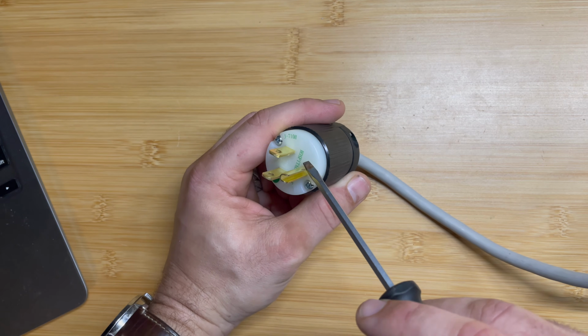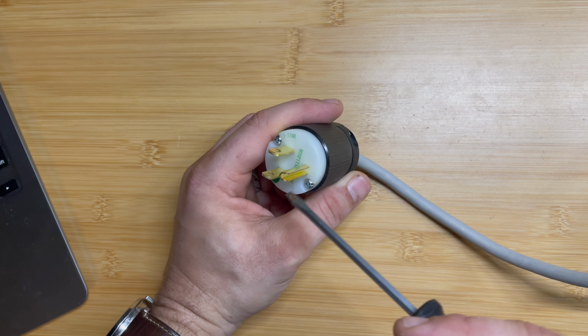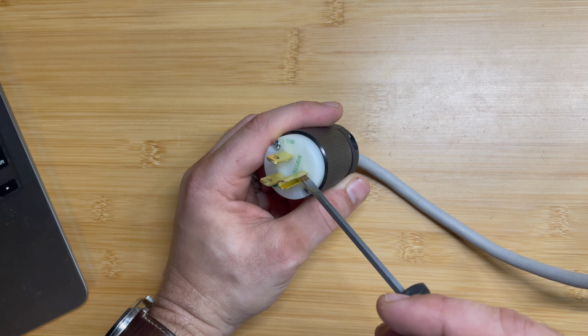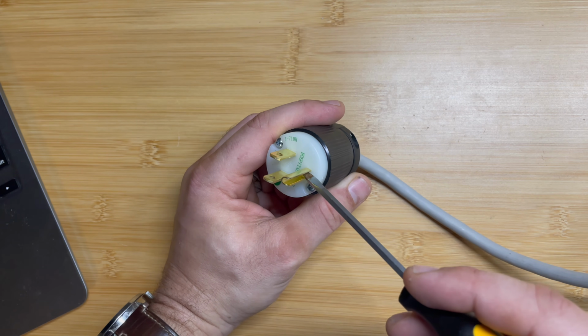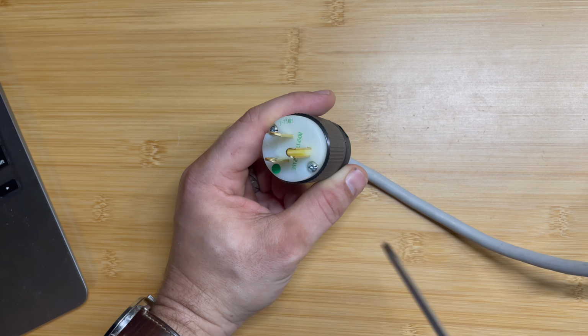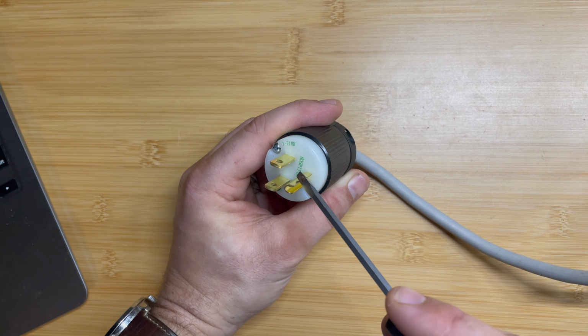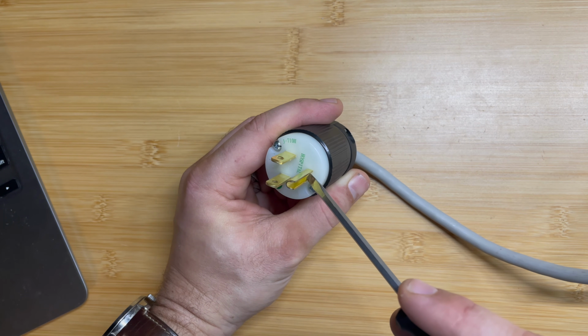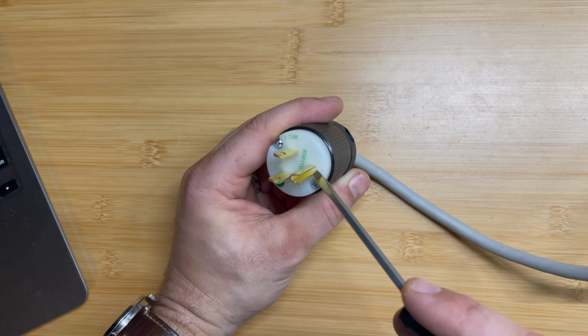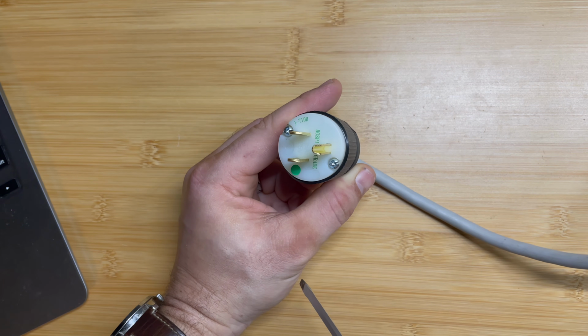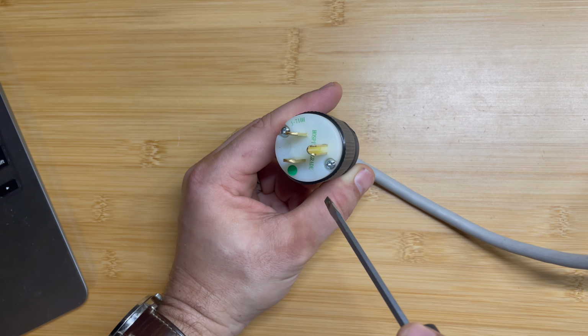Obviously, if you're doing this for a consumer device, this may not be necessary, and it may not be easy to find a location to test this. But if you're doing this on a medical device, you'd want to do a ground resistance check on this cord, and run through your electrical safety tests for medical devices.